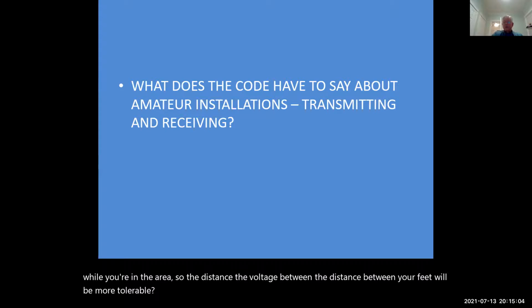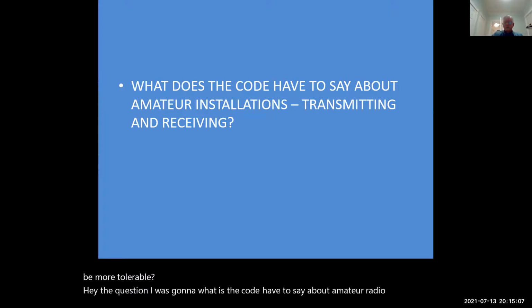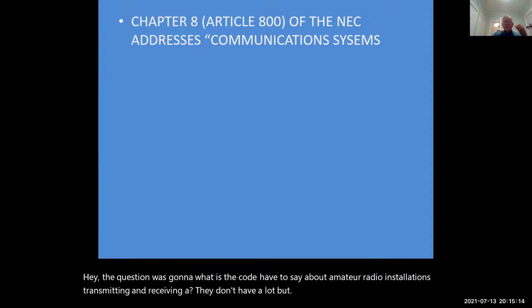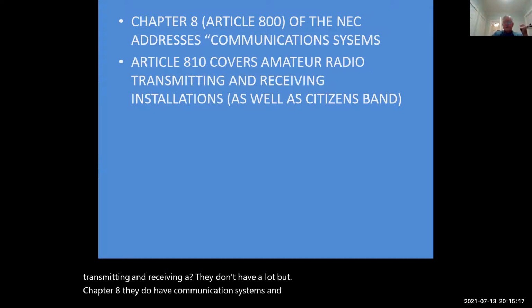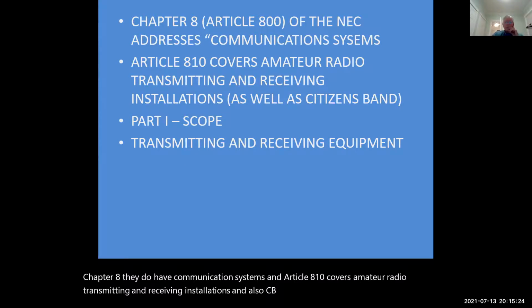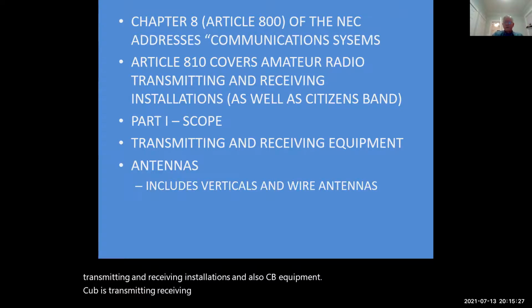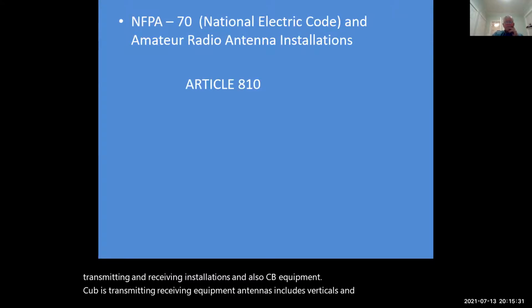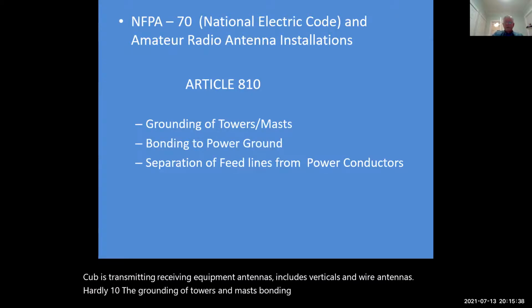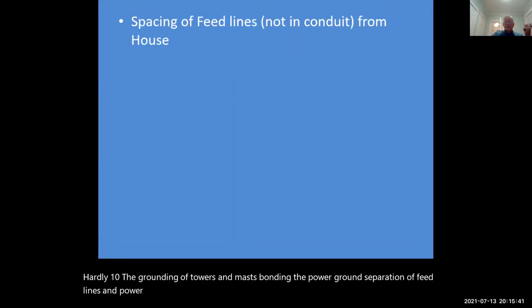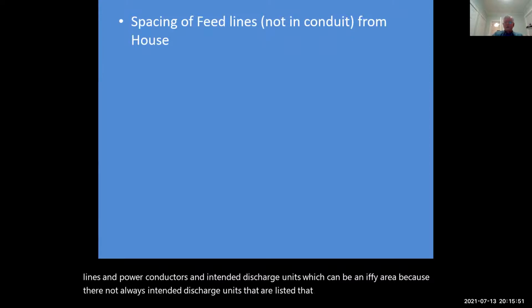The question always comes up: what does the code have to say about amateur radio installations? Transmitting and receiving, they don't have a lot, but in Chapter 8 they do have communication systems, and Article 810 covers amateur radio transmitting and receiving installations and also CB equipment. It covers the transmitting and receiving equipment and the antennas, including verticals and wire antennas. Article 810 covers the grounding of towers and masts, bonding to the power ground, separation of feed lines and power conductors, and antenna discharge units, which can be an iffy area because there are not always listed antenna discharge units available that are suitable for amateur use.